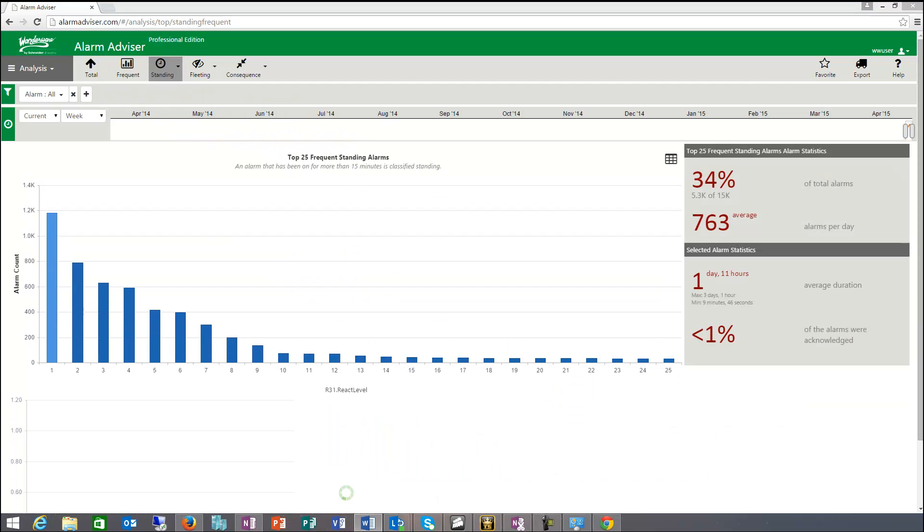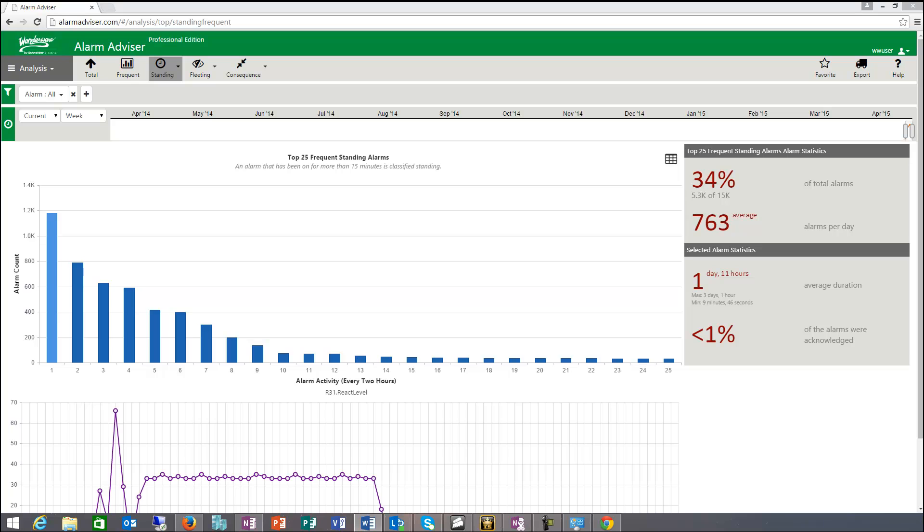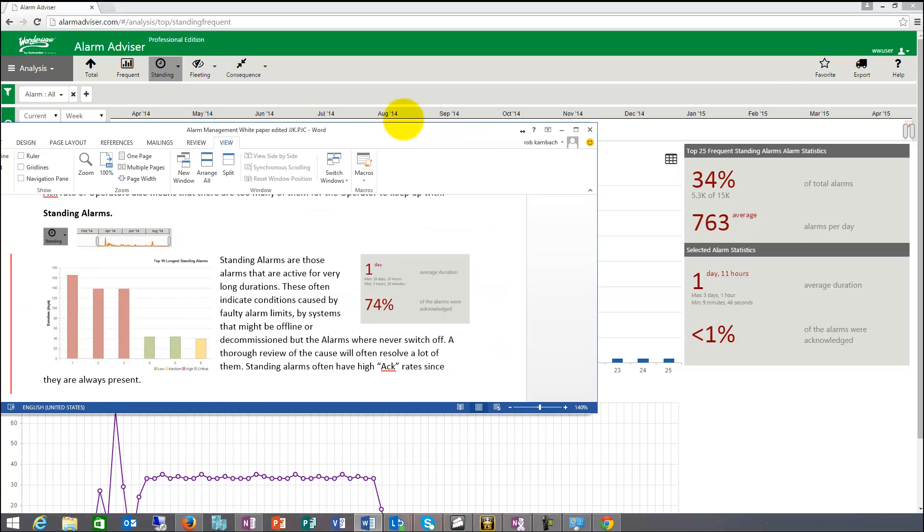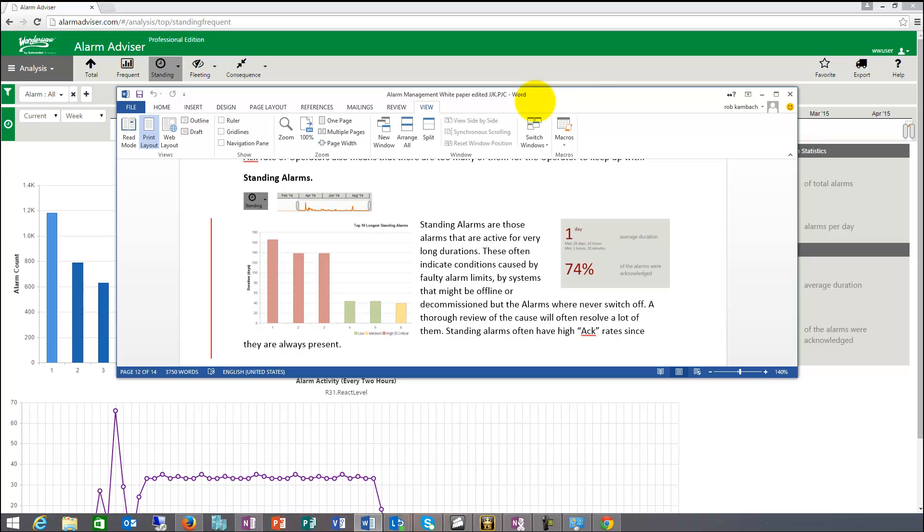Standing alarms are different. So if we take a look at the standing. And standing alarms are really those alarms that are active for very long durations. These often indicate conditions caused by faulty alarm limits by systems that might be offline.